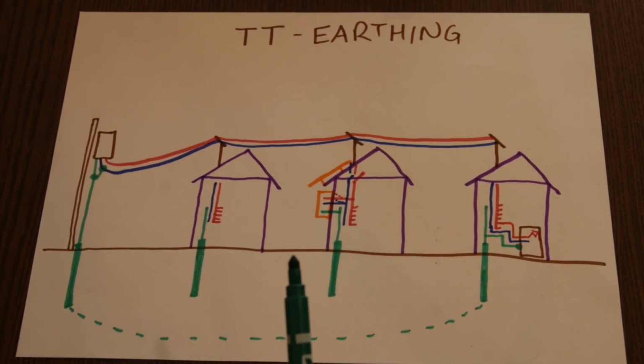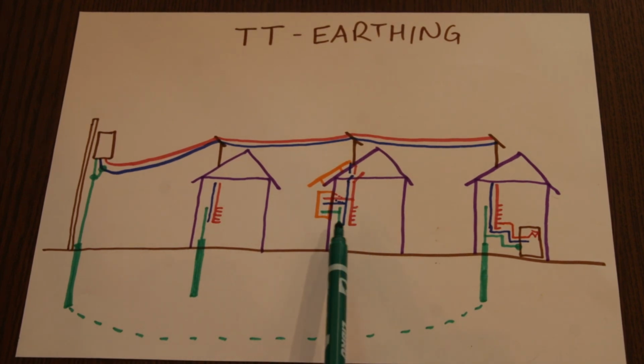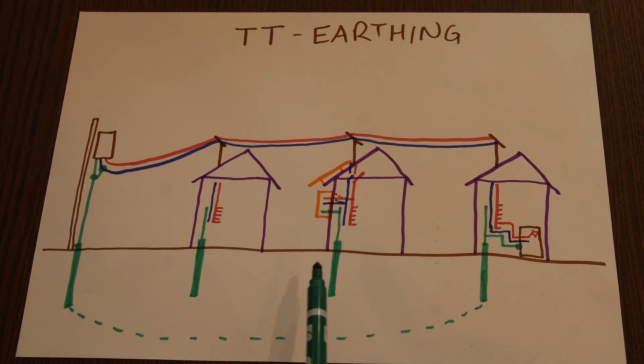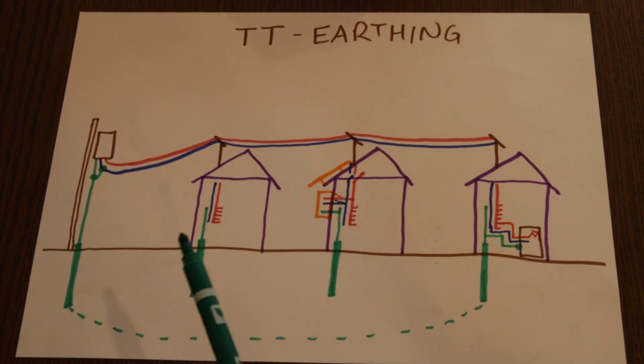What is in general now the problem if we add a second power source? We want to be sure that every circuit in that installation is behaving the same way, no matter which power source is supplying the house. So that means if our grid supply is TT, we have a grounding situation, we have appliances which do have metal cases, we have metal piping there, everything is grounded. We want all of the protective environment to behave exactly the same way, also when the power source is then switched over to the inverter.